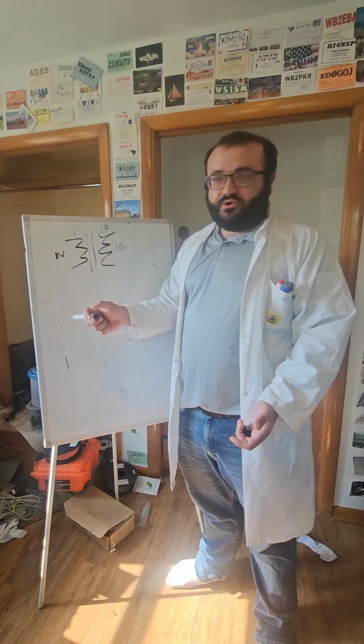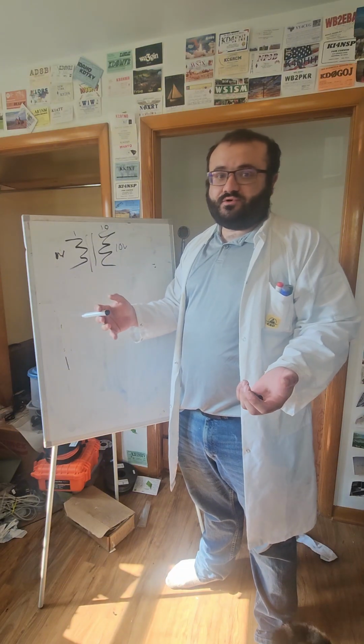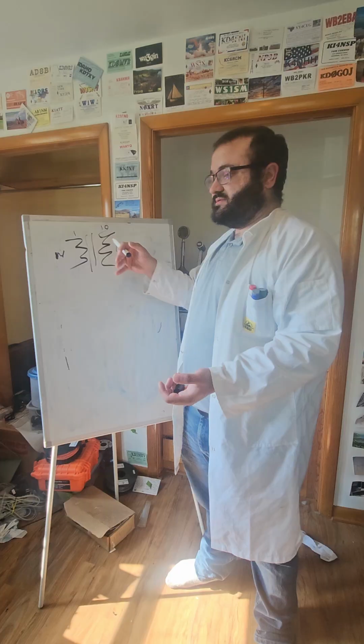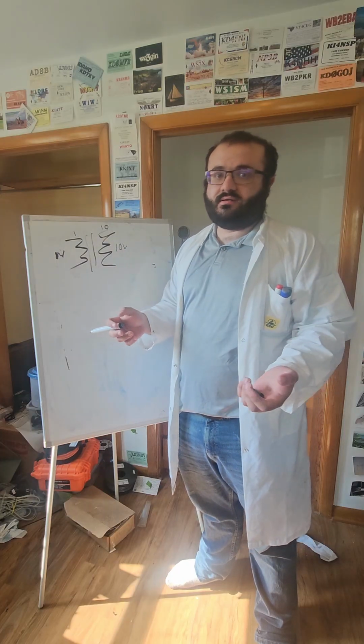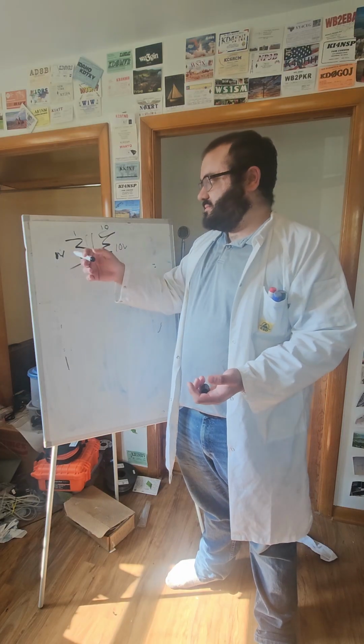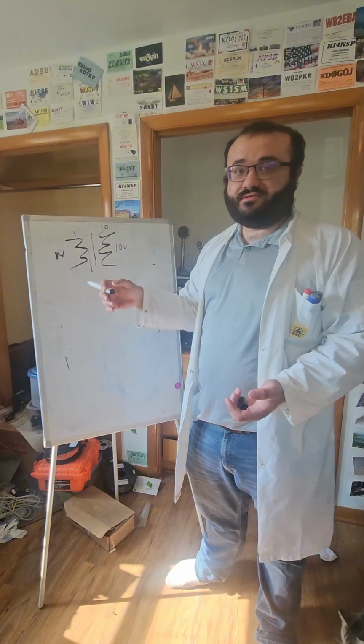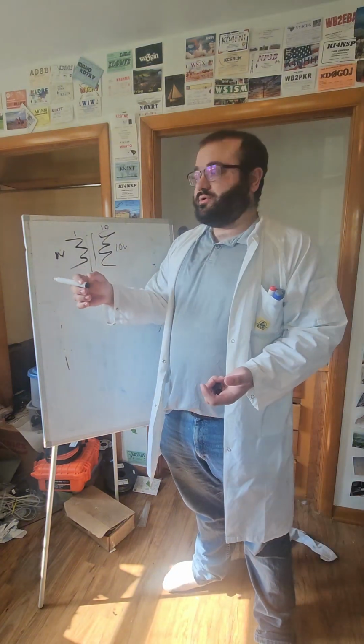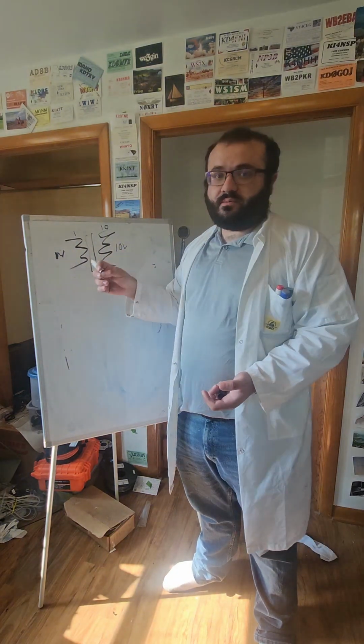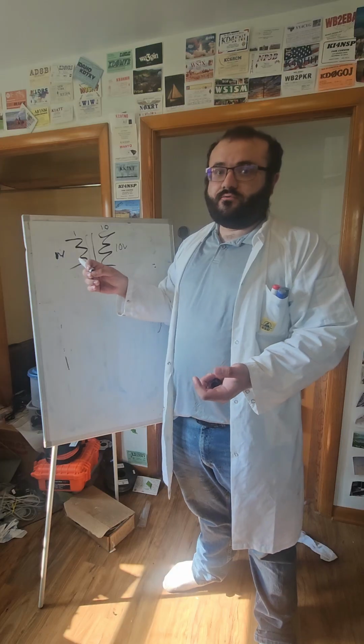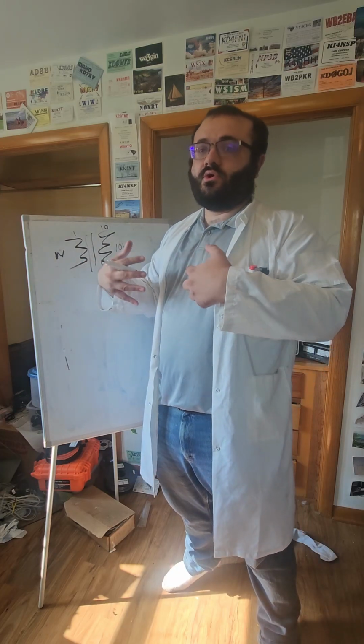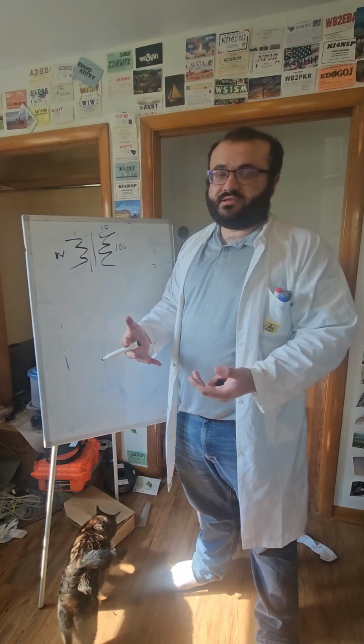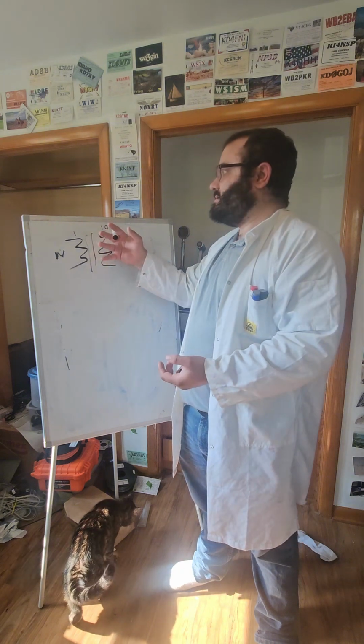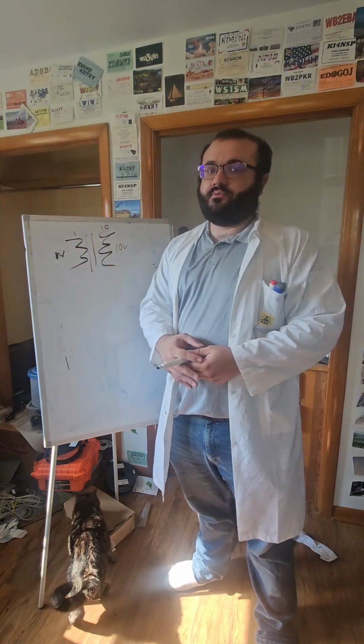With only 1 turn, you would think every transformer you can just have 1 turn and then as many turns on the secondary as you want to get your voltage. Well, the overcurrent of just 1 turn is too much. So you put as many turns as you need on the primary in order to get enough reactance, not to overcurrent the transformer, and then build your secondary how you want it.